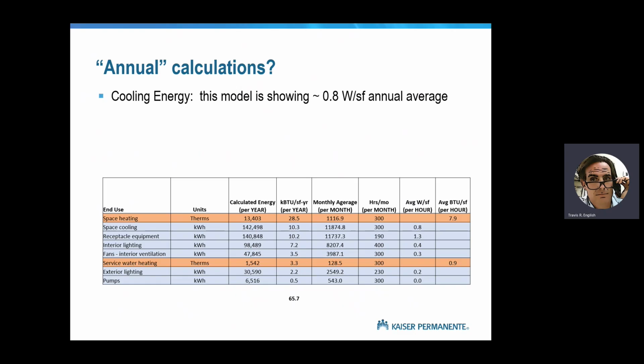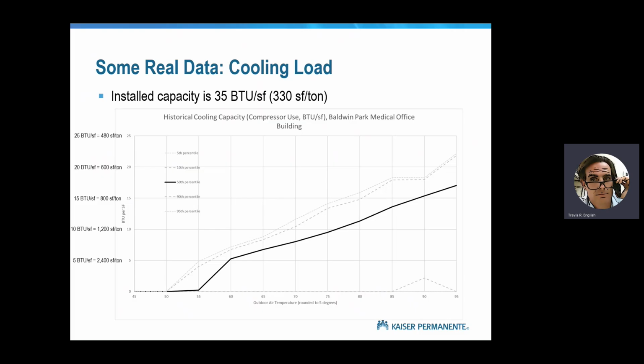Okay, let's move off of fan power. I know we're all HVAC guys, so we want to talk about cooling. So this is the same slide that I showed you earlier, just to kind of break down a cooling number into an hourly number. We divide it out and we look at an annual average hourly number of 0.8 watts per square foot. So put that number in your head for the next 5 minutes, write it down on your napkin, 0.8 watts per square foot. Okay. Here's some real data, same building that I showed you before.